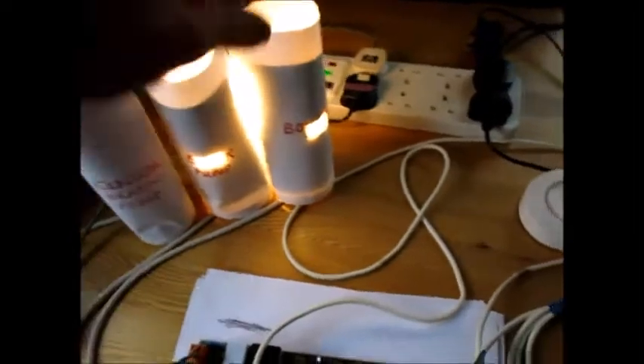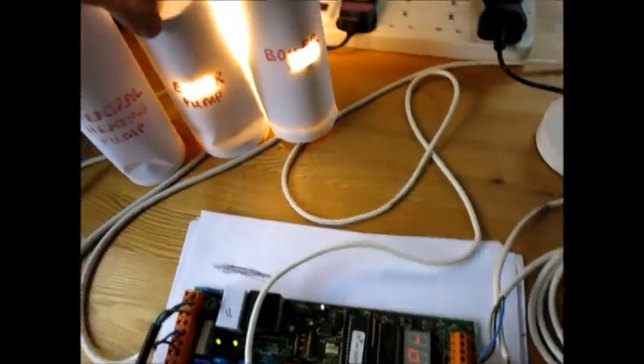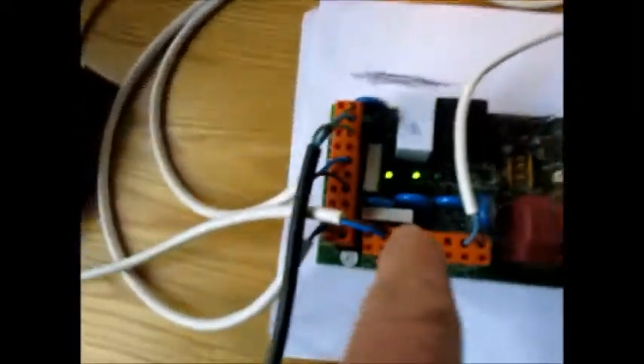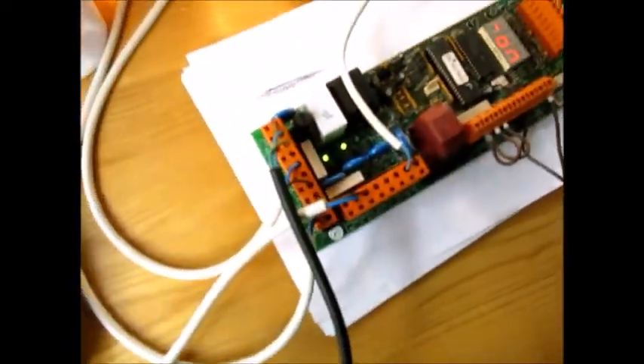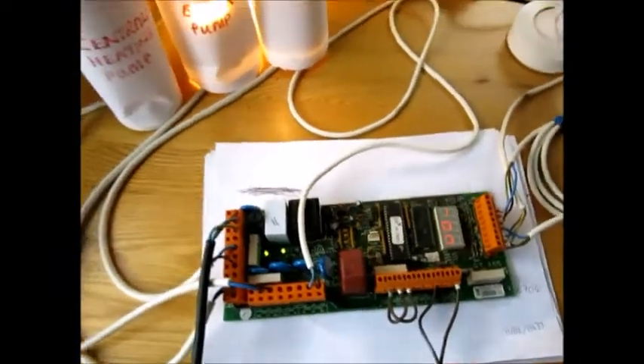You'll notice at the moment the boiler pump and the boiler are on. These two LEDs down here, 3 and 4, show that they're on, which means that the boiler should be fired.